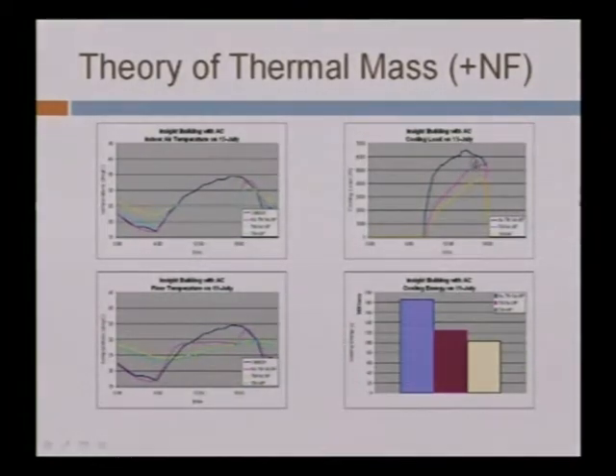With no thermal mass, the dark purple line has a very high cooling load. The pink line is thermal mass without night flush, and the yellow is thermal mass with night flush. As you can see, there is a reduction in the peak cooling load. Put simply, we don't need big air conditioning.